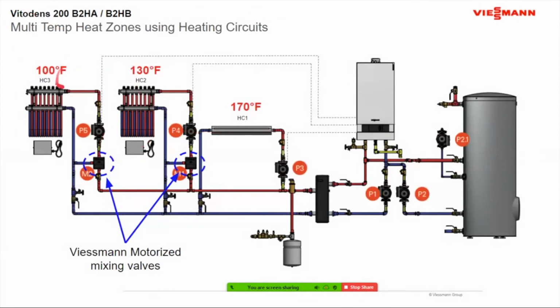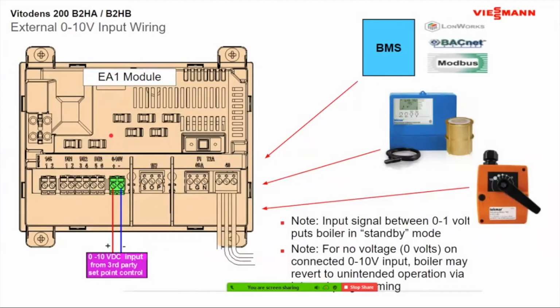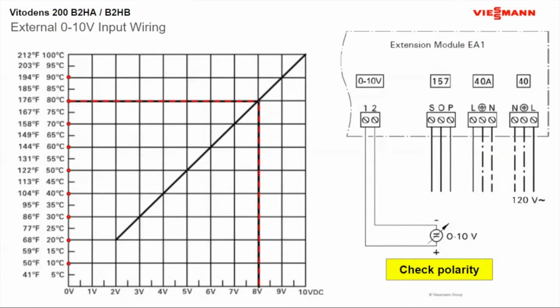Just remember, if you are doing HC circuits, HC1 is always going to be for your highest temperatures. It's going to be a fixed temperature for the highest temperature. These are going to be your mixed temperatures, HC2 and HC3. And if you're receiving a 0 to 10 input from these types of things, this is where you're going to tie in your 0 to 10. And with ours here, 0 to 10 usually shows in voltage, but each 1 volt is, I think, 10 degrees, as you can see here. It is polarity sensitive as well, so you're going to have your plus to plus, minus to minus, or red to red, blue to blue, whatever color you're using.